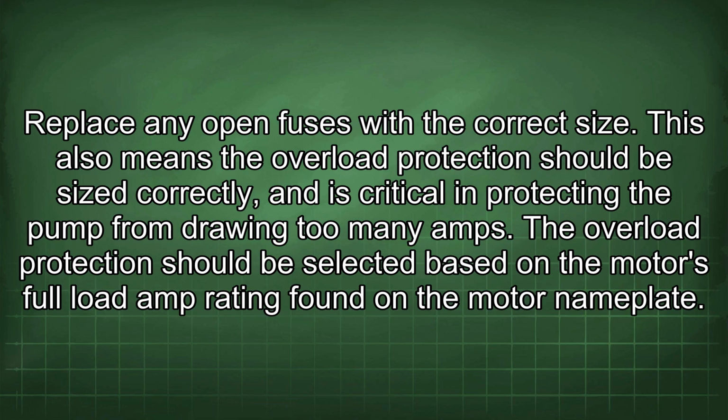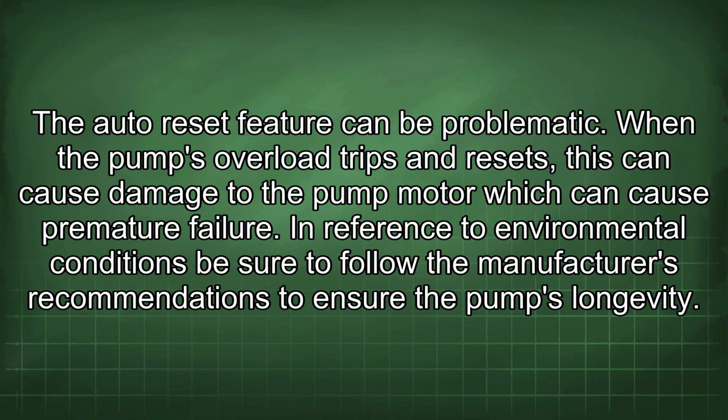This also means the overload protection should be sized correctly and is critical in protecting the pump from drawing too many amps. The overload protection should be selected based on the motor's full load amp rating found on the motor nameplate. The auto reset feature can be problematic. When the pump's overload trips and resets, this can cause damage to the pump motor, which can cause premature failure.